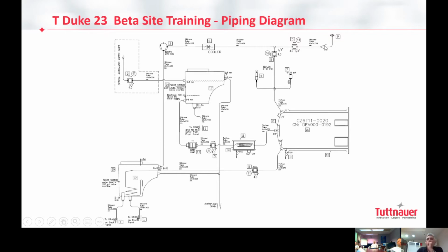What happens? It's like a flash of air, because at this point there is deep vacuum, right? Because we already created vacuum. On this side, air will come from the ambient, so it will just press and push, kick out the air and the condensate from the pump into the water tank. Of course, this must be closed. Otherwise, if this one is open, when the air is coming, it will break the chamber pressure too. So we will close it before opening this one.